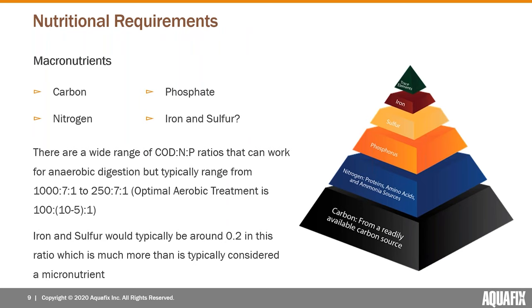Regarding nutritional requirements: macronutrients are carbon, phosphate, nitrogen, and arguably iron and sulfur. Iron and sulfur aren't directly toxic and you can add quite a bit without impairing function. However, sulfur-reducing bacteria compete with methanogens and produce hydrogen sulfide, limiting methane quality — the higher your sulfur levels, the more iron you'll likely need to precipitate out excess sulfur. The COD:N:P ratio for anaerobic digestion is roughly 1000:7:1, compared to aerobic's approximately 100:10-5:1.